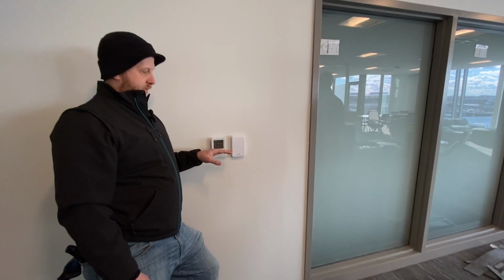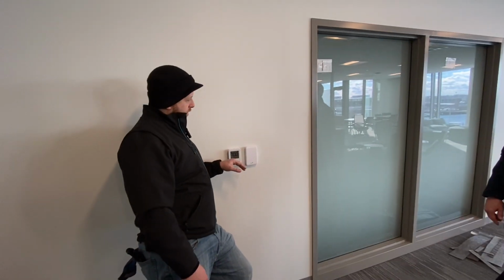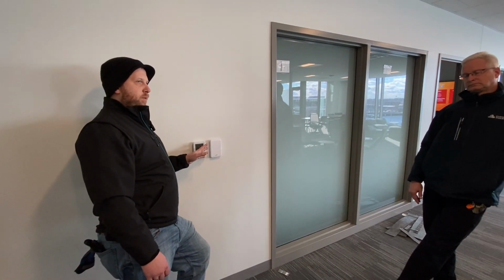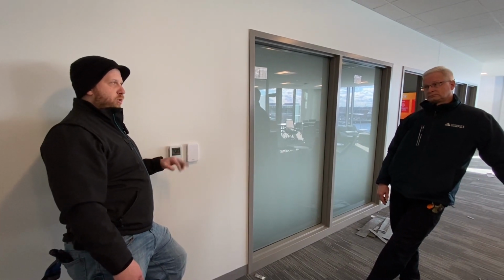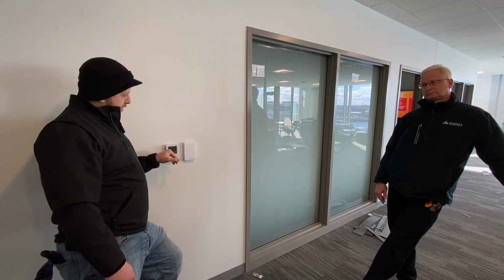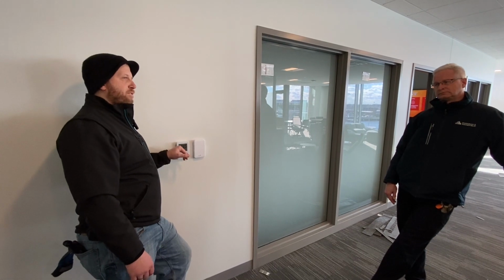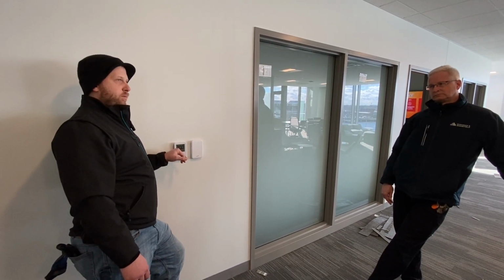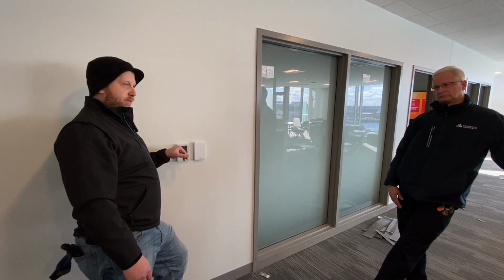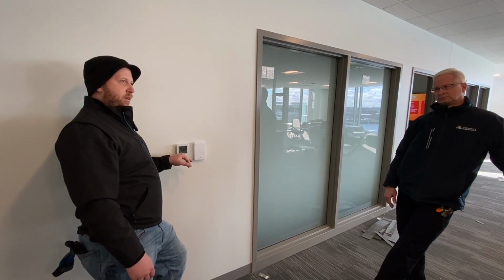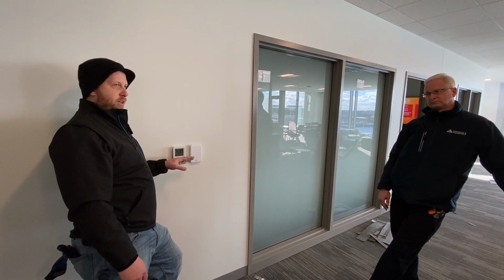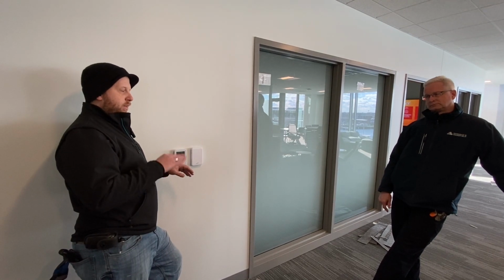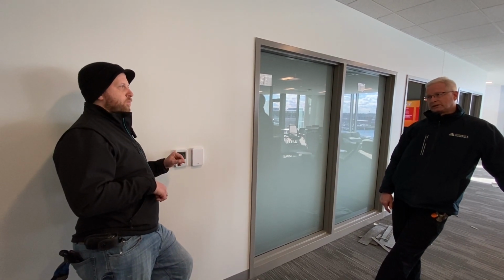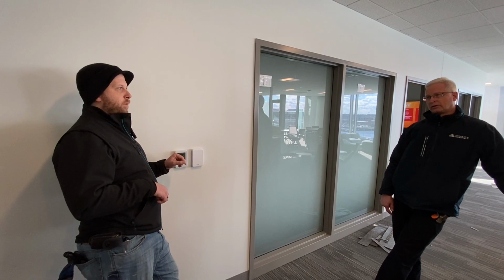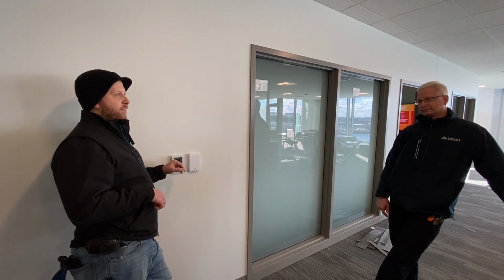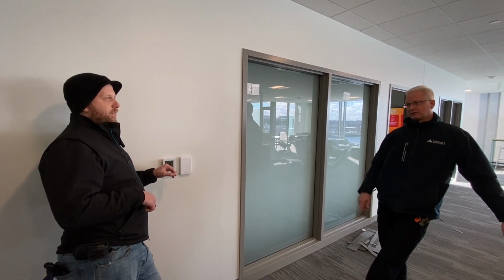The thing that makes people always question is that it has a deadband built into it. It's a 4-degree deadband, 2 degrees high and low. So if somebody sets it to 70, we're effectively going to try to heat up to 68. So if somebody puts in 70, and says it's not getting to 70, it's only 68, well, it's working perfectly because we're not meant to get to 70. Can we change the deadband? Yep. Let's change the deadband to 1 on all of them. 1 degree each way, 2 total.